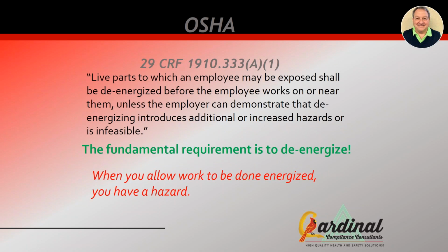They want you to de-energize. If that panel has been put in an electrical safe work condition, there is no hazard. OSHA draws a line at 50 volts and under. Yes, there's the potential for short circuits, heating, and burning, but 50 volts is not enough to be a shock hazard. And with arc flash, 50 volts is not enough to cause an arc flash that puts you into category 1.